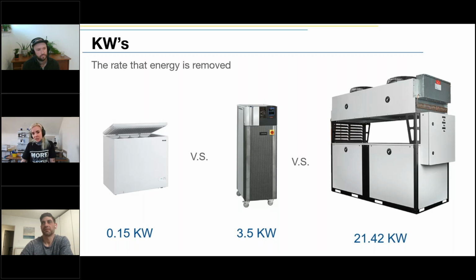That big chiller on the screen from G&D versus the Huber in the middle - the G&D is fundamentally cheaper than the Huber. It costs more for you to install compared to uncrating a chiller and rolling it into the room. But if your chiller's on wheels, it's because it needs repairs, because it has to be moved from service often. You want to look at this equipment from a more long-term and scalable perspective.